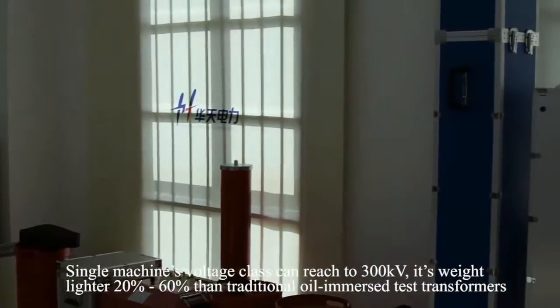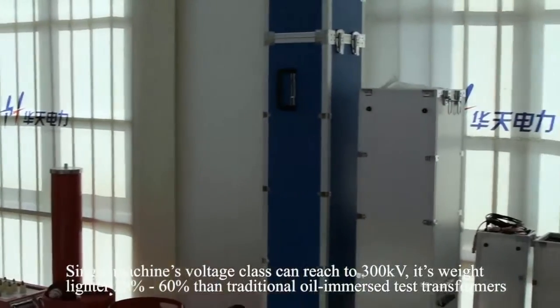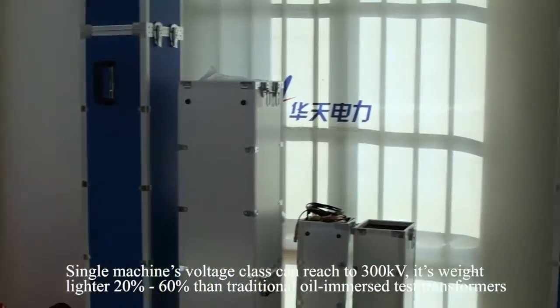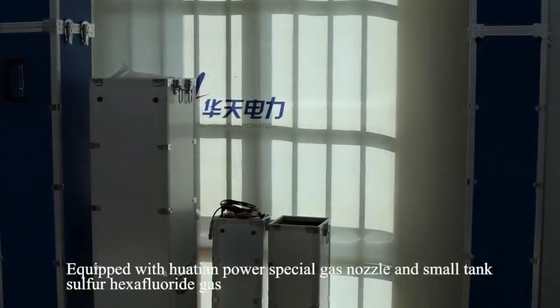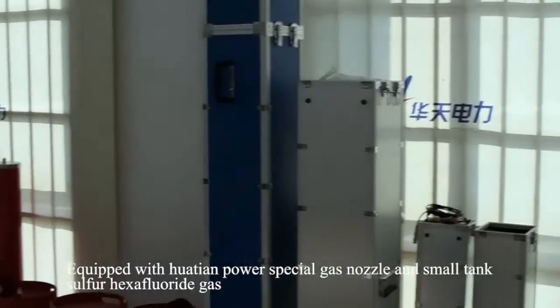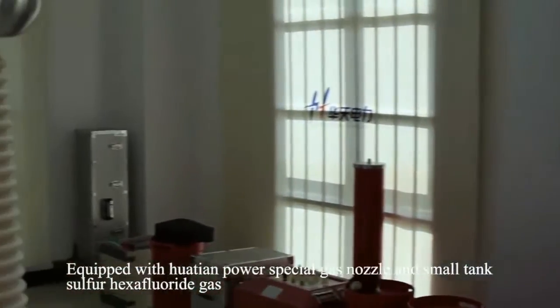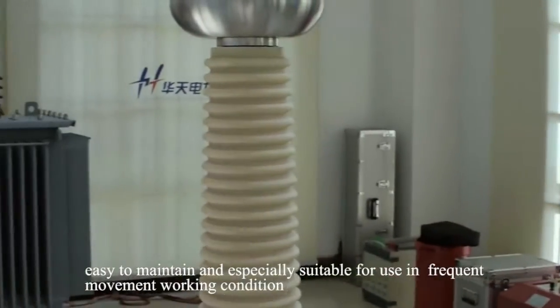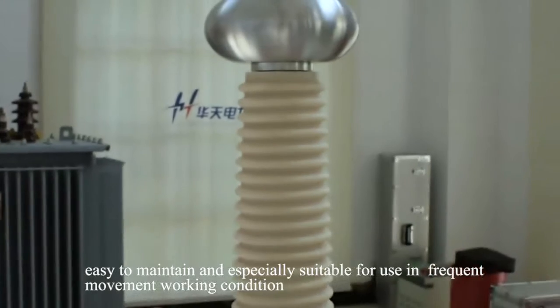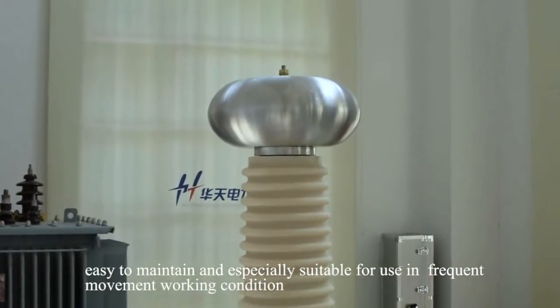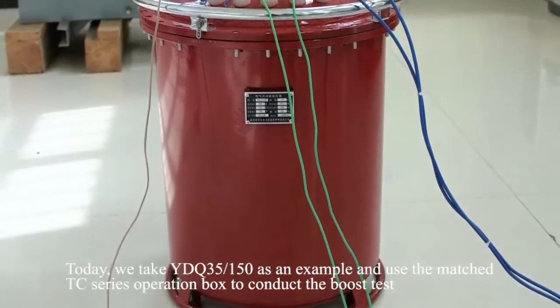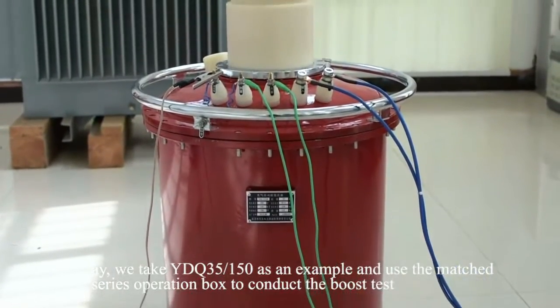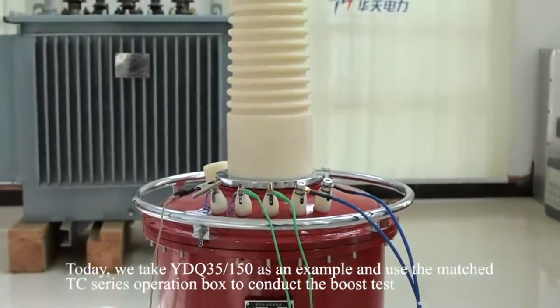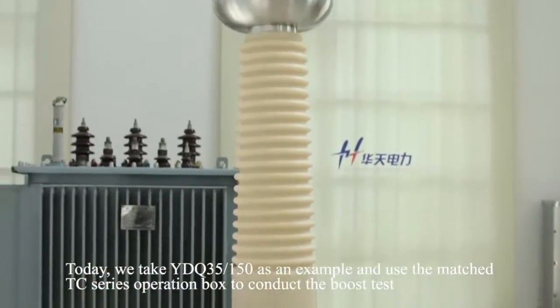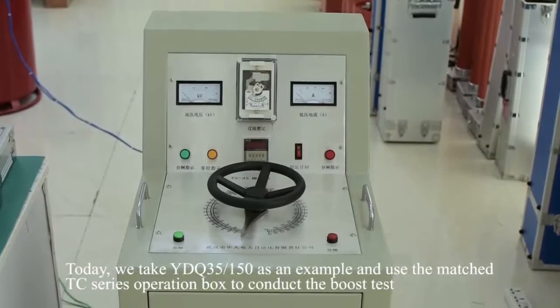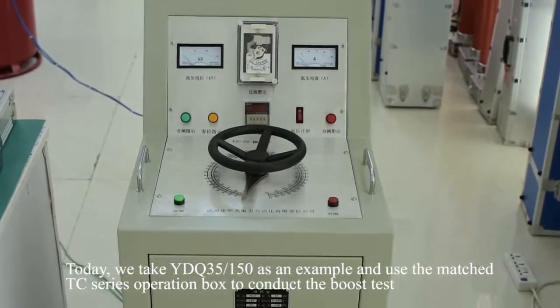It weighs 20% to 60% lighter than traditional oil-immersed test transformers. Equipped with a special gas nozzle and a small tank of sulfur hexafluoride gas, it is easy to maintain and especially suitable for use in frequent movement working conditions. Today we take the YDQ35/150 as an example and use the matched TC series operation box to conduct the test.